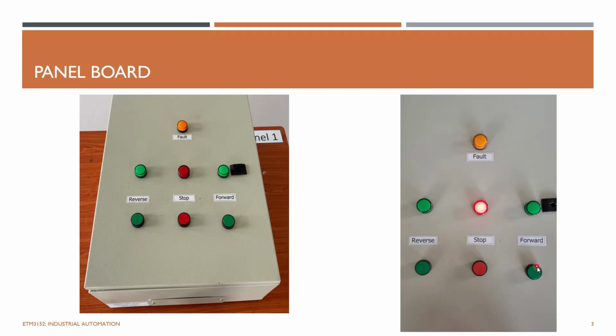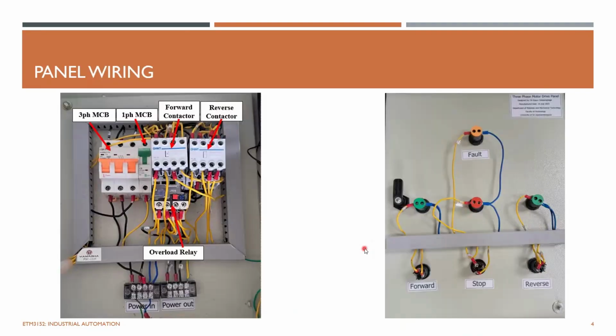And if you press this forward button, it will not run the motor in the forward direction, because, as you have just learned, there's an interlock. So if you want to run the motor in the forward direction, you have to stop the motor, then click this one. Either way, whether the motor is running in one direction, you have to stop it and then run in the opposite direction.